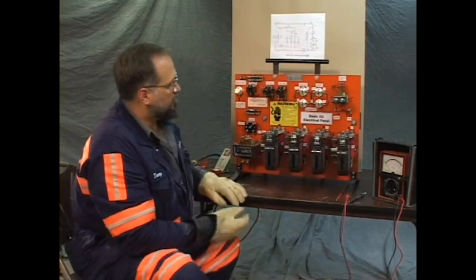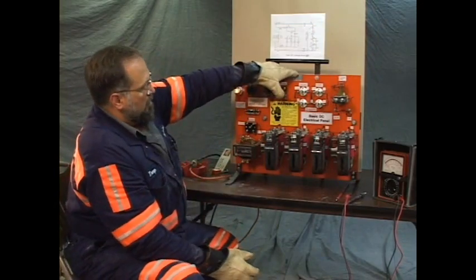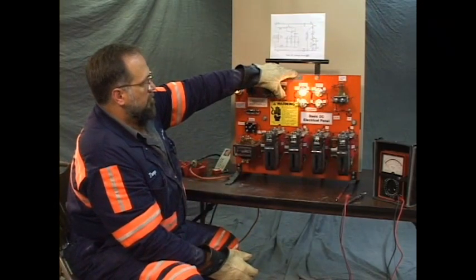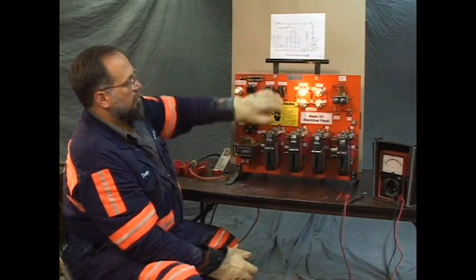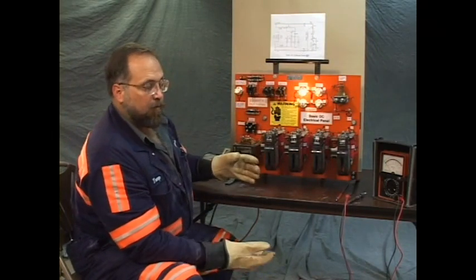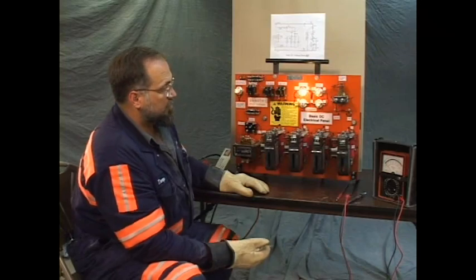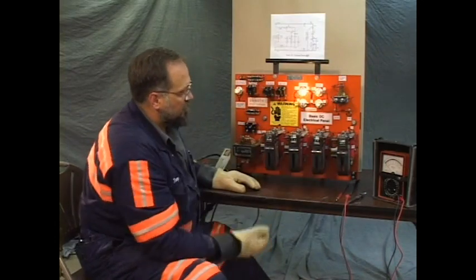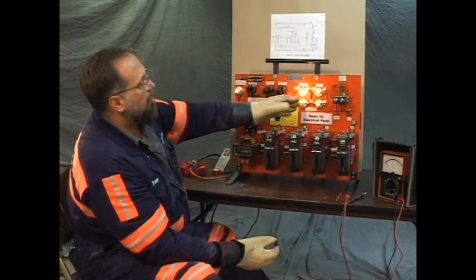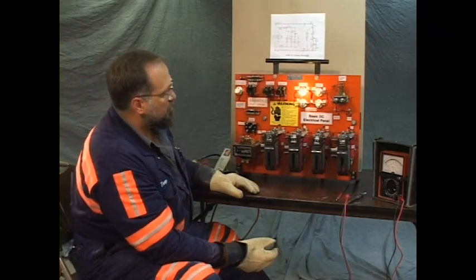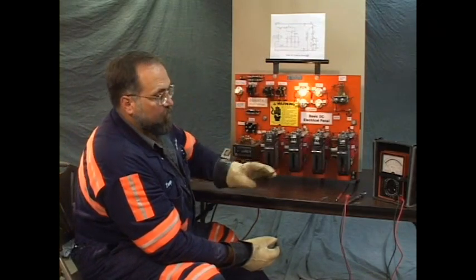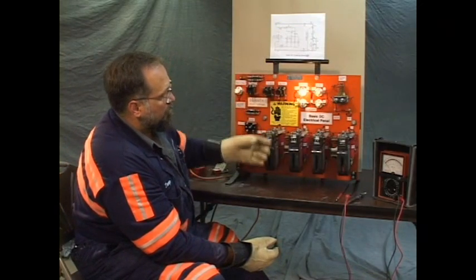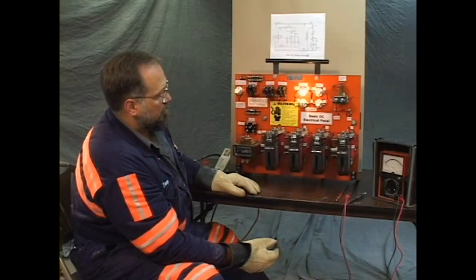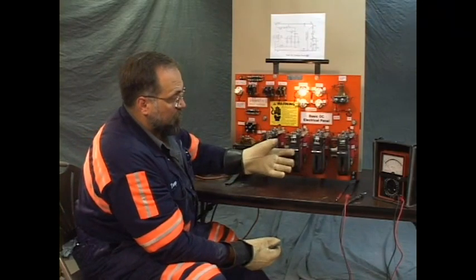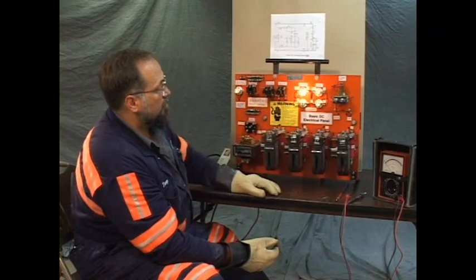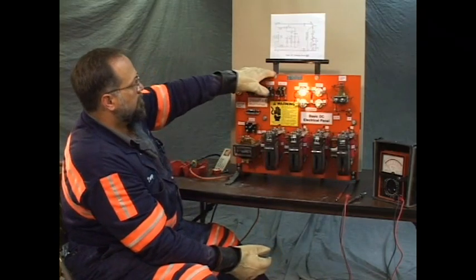Here we go. When we start at this time, well, we noted only 2 clicks. M1 and M2 closed. Anytime you have a light at all, M1 and M2 are both closed. Then after a 1 second interval, 1A picked up, this light went off. And we're still waiting, but 2A is never closed. I don't believe it's gonna.